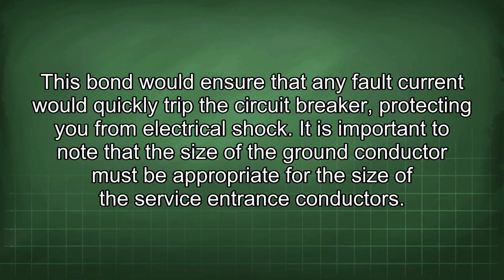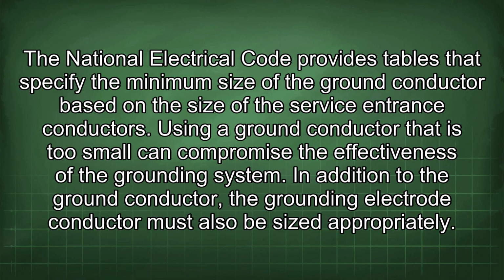It is important to note that the size of the ground conductor must be appropriate for the size of the service entrance conductors. The National Electrical Code provides tables that specify the minimum size of the ground conductor based on the size of the service entrance conductors. Using a ground conductor that is too small can compromise the effectiveness of the grounding system.